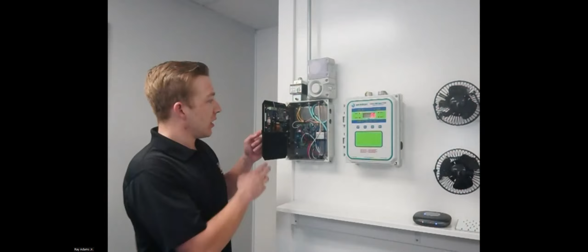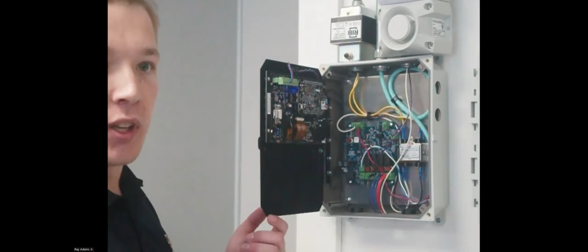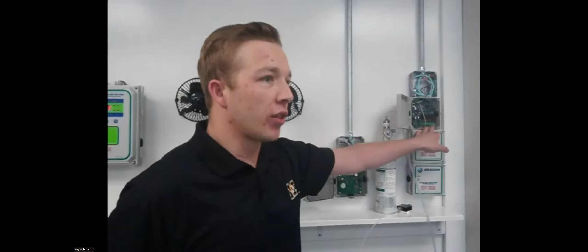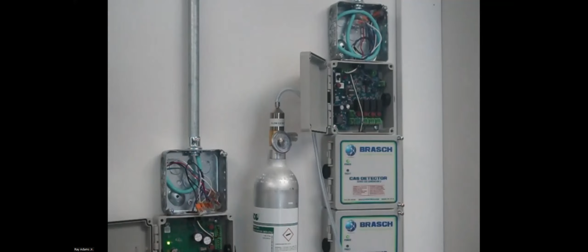Now, one particular thing that we wanted to incorporate with the control panel from an installation side was the ability to take the relays and mount them remotely from the control panel. So as you can see on the inside of our panel here, we have a circuit board that has 4 dry contact relays on it. That board is what we put in a remote box over here to the side, and we call that our expansion pack. Again, it's the same board that you have inside the panel, but it allows you to take these dry contact relays and mount that expansion pack directly next to where your fans are within a facility.